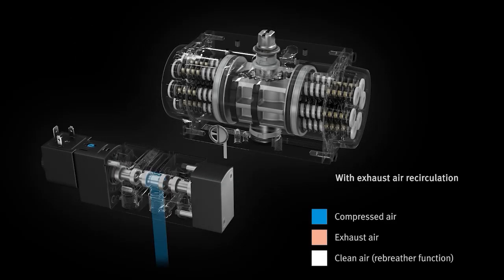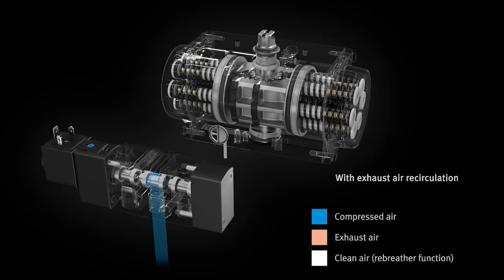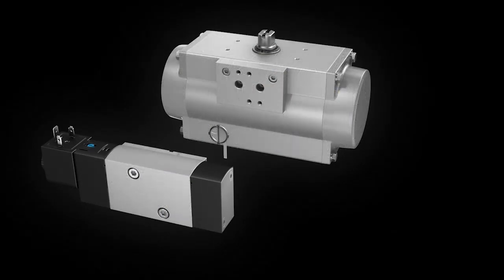With exhaust air recirculation, the integrated exhaust air is recirculated for the spring chamber and this ensures that no atmospheric air is taken in. This protects the spring chamber and the springs of the actuator against corrosion.